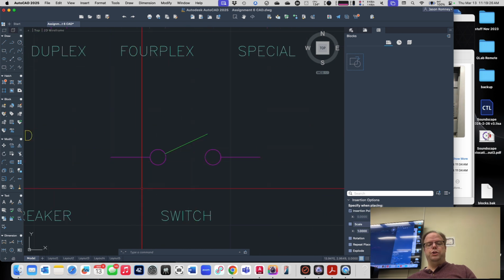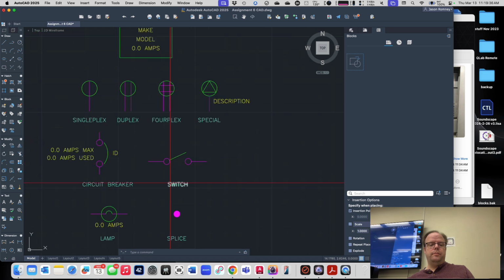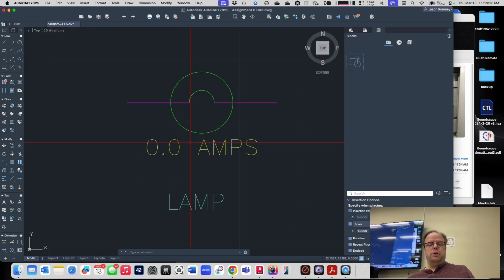Sometimes you'll have switches on things, to switch a rack on and off, like on a power conditioner. So this is the drawing for a switch. Sometimes our power conditioners have little lights or lamps on them so that you can see in the dark. And those draw a little bit of current, usually about 0.5 amp if they're the incandescent ones. So you're going to want to have that on there and make a drawing for this.